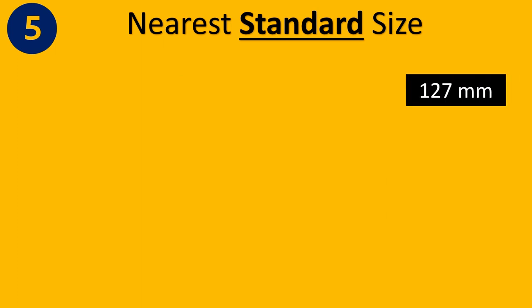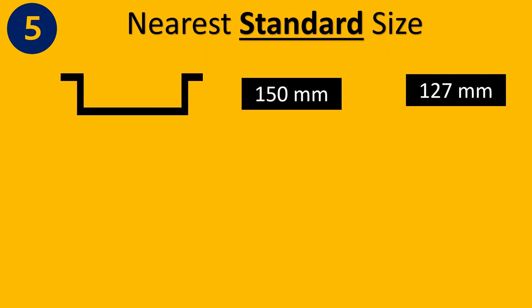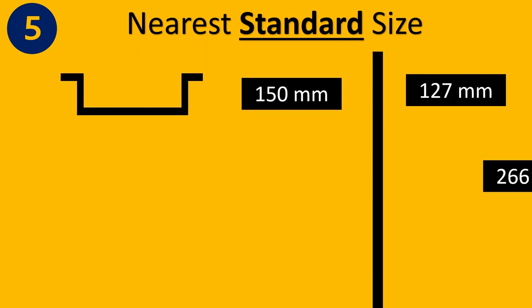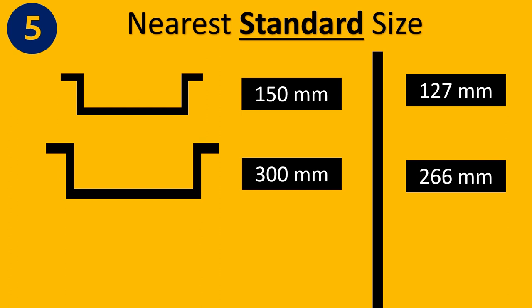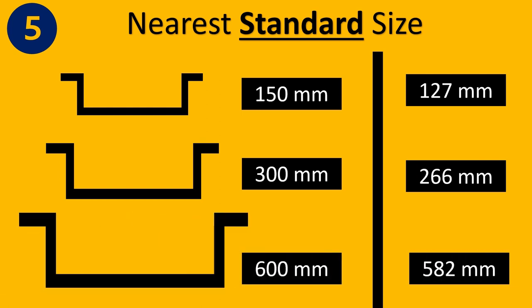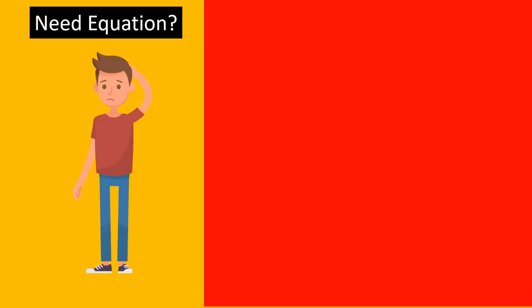Step five is knowing the nearest standard size. Once you have your final calculation from steps one through four, you round up to the nearest standard size. For example, if your calculation gives 127 mm, you go for 150 mm; if it gives 266 mm, you go for 300 mm or 600 mm — whatever is the nearest standard size.